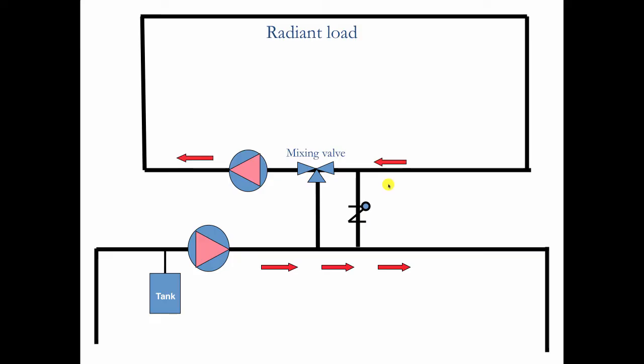So now this is the challenge with using a mixing valve. The flow is going this way. The hot water comes up, the cold water comes down. The return water has a choice of either going back to the radiant, mixing with hot water to keep the temperature up, or going completely back into the primary flow if the radiant load is satisfied on temperature. So it's continuous circulation and we're varying the temperature.